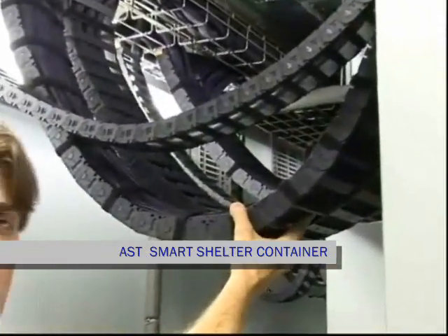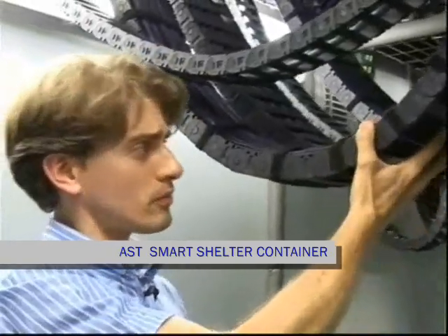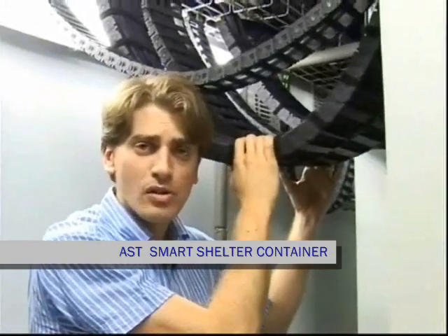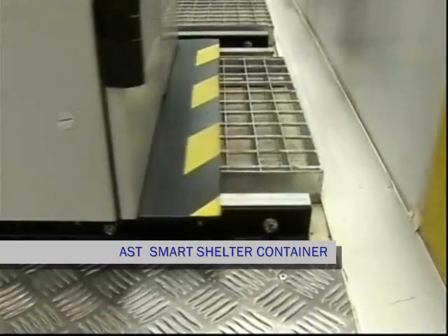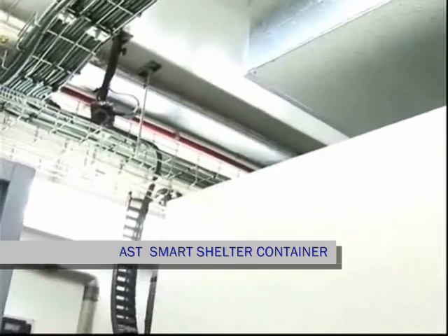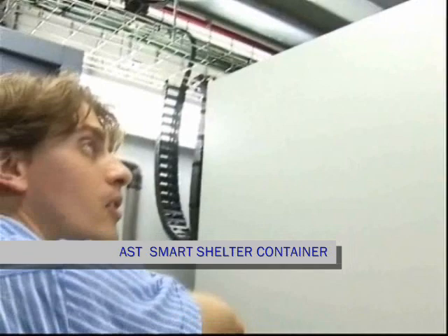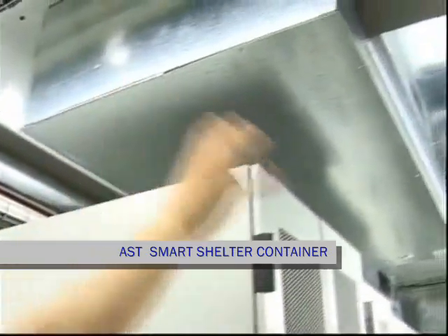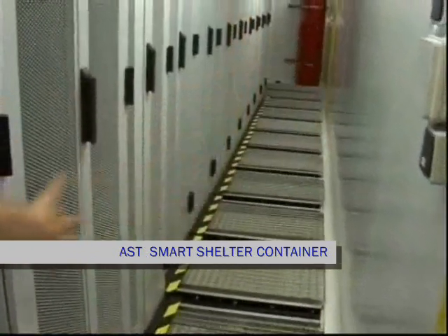For example, this E-chain system is capable of holding up to 300 cables in one of these chains. So at the end of the day, any type of configuration, cabling, as well as communications or power cabling can be installed in this container. So moving these racks back into their rest position, we can see how the cooling system works. Basically, what we have assembled here in order to provide 8 kilowatts per rack are overhead fan coils, which take hot air from the hot corridor on the backside, cool it down, and bring the fresh air into the cold aisle, and then back into the servers, providing, again, this 8 kilowatts per rack.